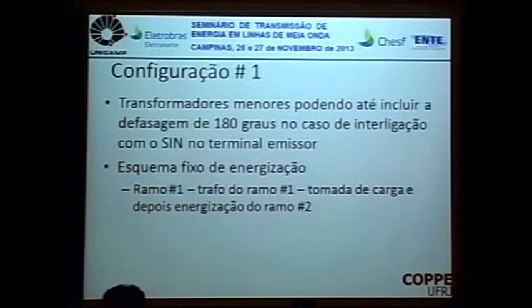It's important to remember that in Brazil, the half wavelength plus would possibly have two connection points, one in the emission terminal and the other in the receiving terminal, due to how the system is organized. So possibly we'd have that 180-degree transformer being necessary. With more branches, we would have smaller 180-degree transformers that would be cheaper, of course.